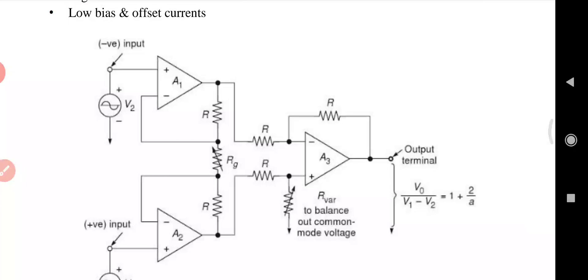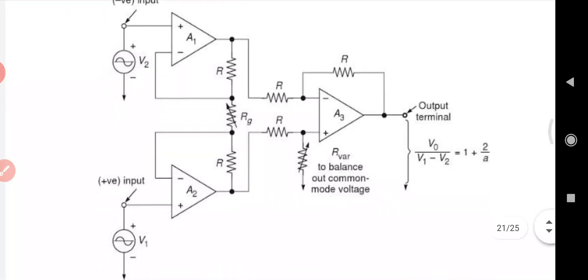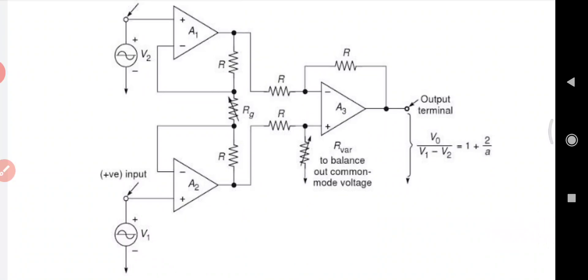Op-amp A3 with four equal resistors R forms a differential amplifier with a gain of one. The variable resistor R_variable is used to balance out any common mode voltage difference. R_g is used to set the gain using the formula: V0 / (V1 − V2) = 1 + 2R/Rg. V1 is applied to the positive input terminal and V2 to the negative input terminal. V0 is proportional to the difference between the two input voltages.